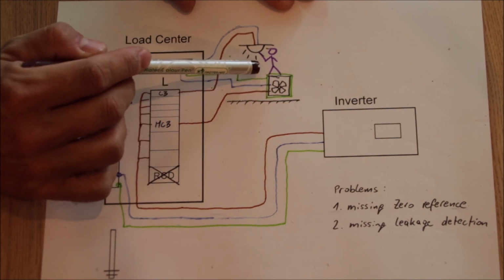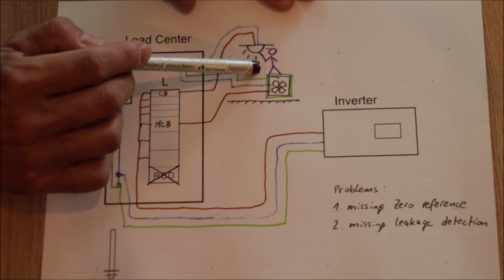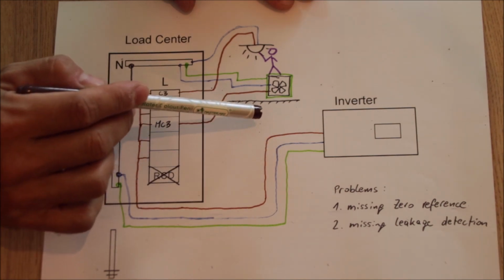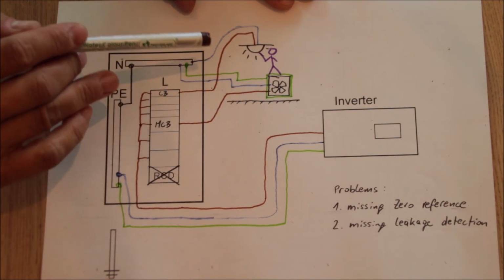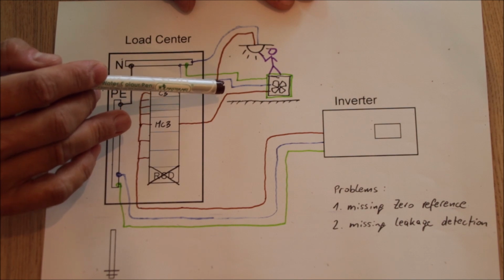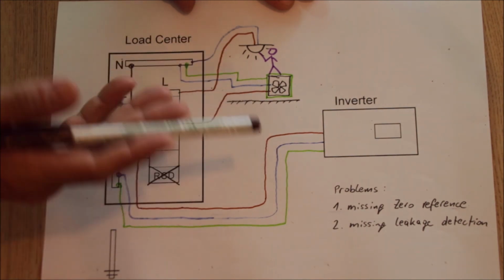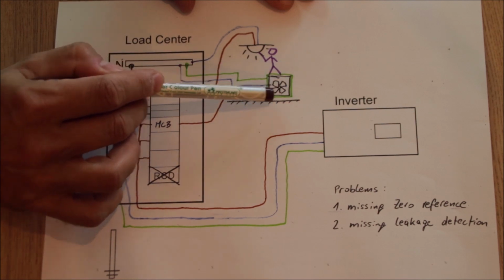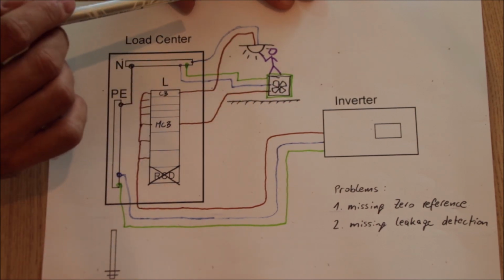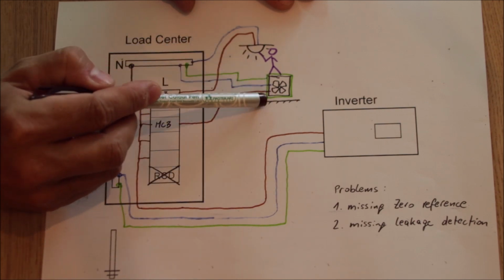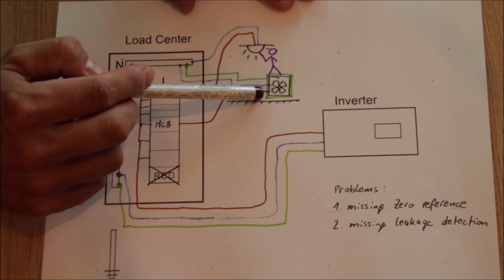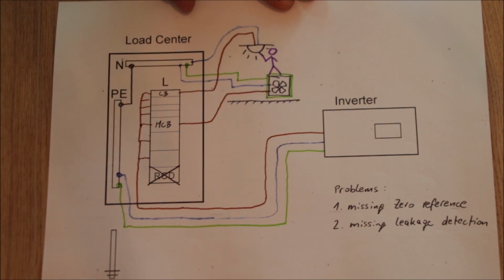So what he has done is he has exposed one of the two active ones, and this is an absolute no-no in a housing installation. There can now be two issues with that, as we have exposed neutral here to the outside. The first issue: because of the missing zero reference, there could actually be voltage now on this unit from the outside.